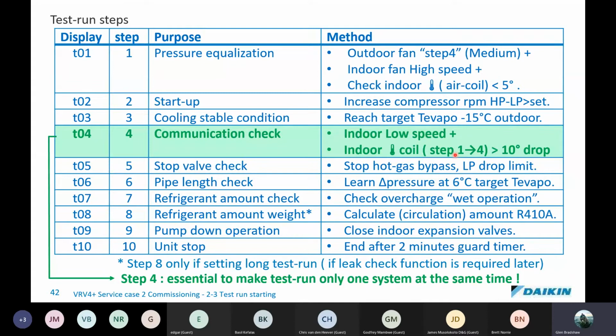Then T04 is a communication check. Here indoor goes to low speed, and it checks the indoor temperature and the coil, step 1 to 4, and it must see a greater than 10-degree drop, which we would expect as long as there are no blockages in the pipe. This is why it's essential to only run one system at a time, because if more than one system is running, they can all give that variance of 10-degree drop, and then the systems will never know whether they've got any swapped piping.